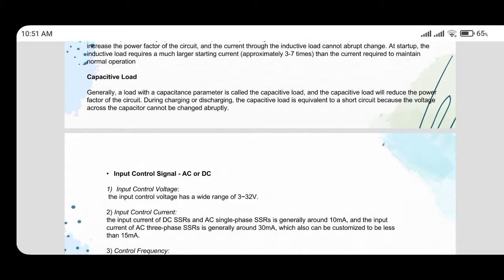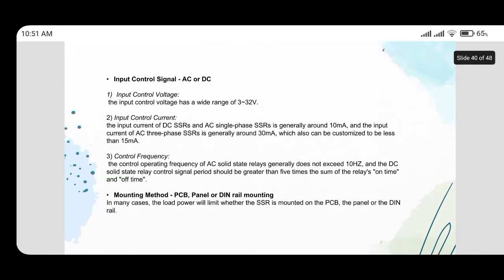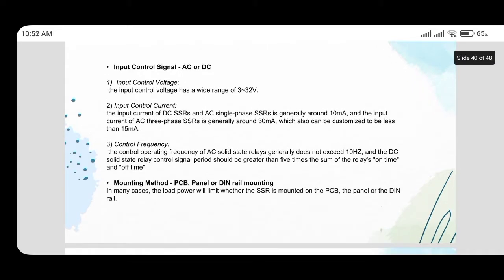Input control signal, AC or DC. First, input control voltage. The input control voltage has a wide range of 3 to 32 volts. Second is the input control current. The input current of DC SSRs and AC single phase SSRs is generally around 10 milliamps, and the input current of AC three-phase SSRs is generally around 30 milliamps, which can also be customized to be less than 15 milliamps.